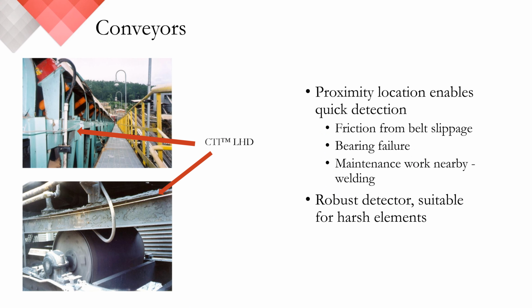Conveyors are a common application. Some of the issues we see in these areas include bearing failures and belt slippage, both of which could cause overheating and potential fire. With its unique construction, linear heat can be used to provide proximity detection to these areas to detect and react as quickly as possible.